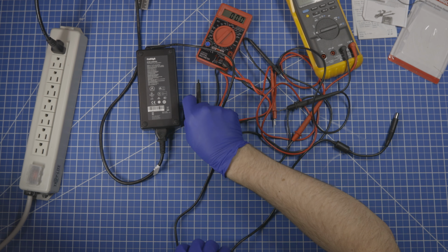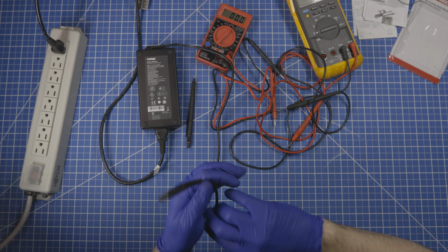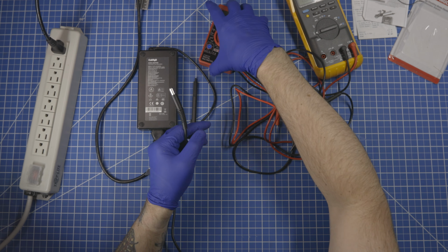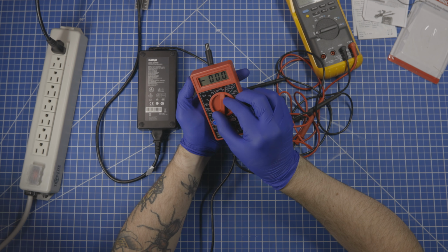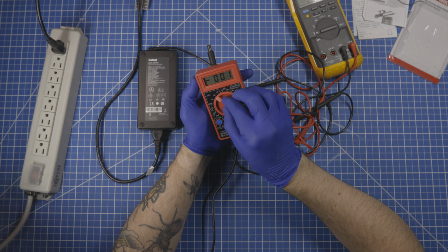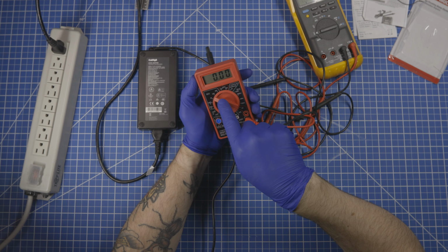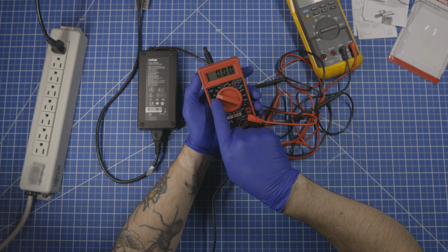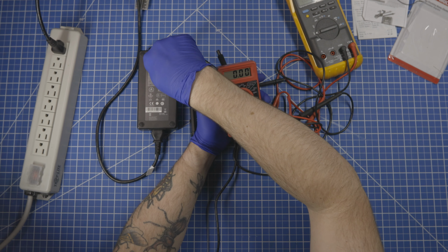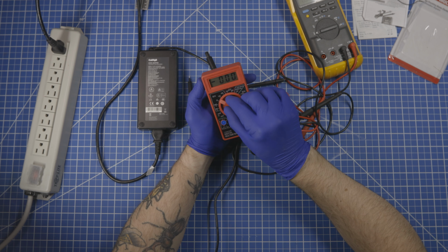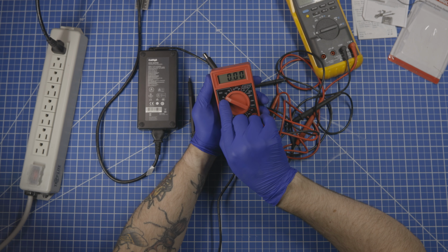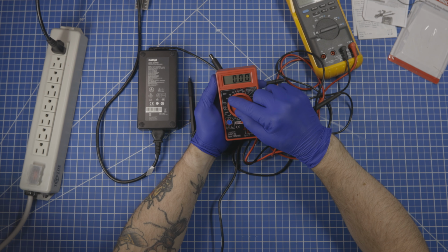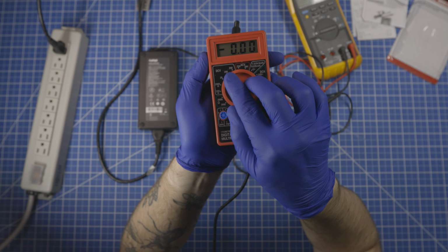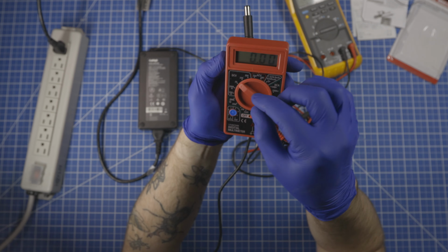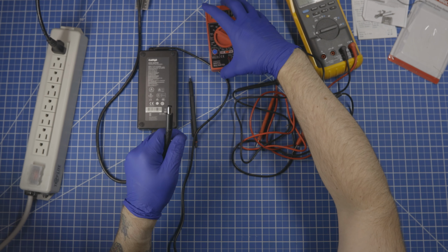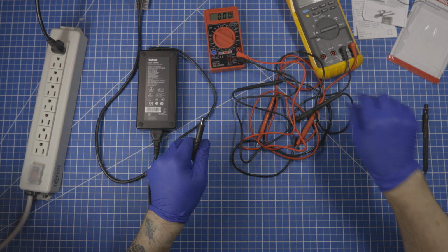So this is DC because it is doing an AC to DC conversion. So we need to switch our device to the 20. Now, this is supposed to output 20, so we're kind of in a weird spot since this is saying 20 or less, and this next option of 200 is saying between 20 and 200. So we'll choose 20. If it reads over limit, we'll make an adjustment.